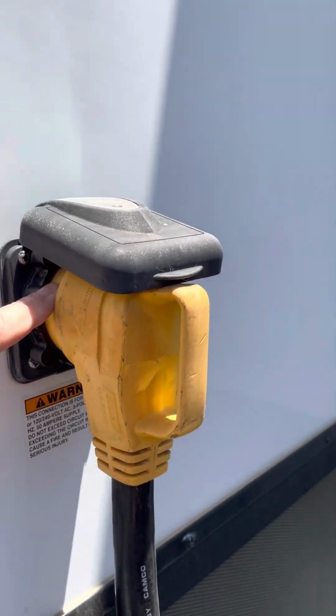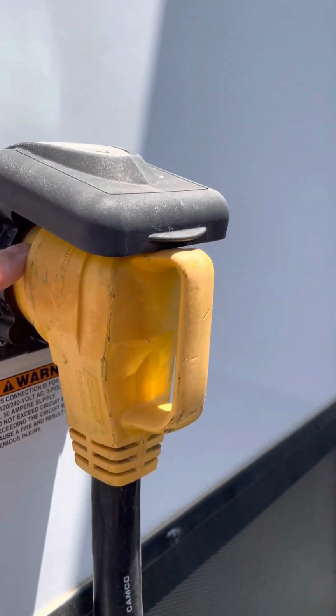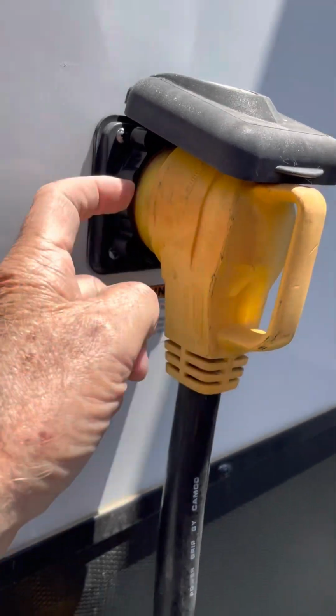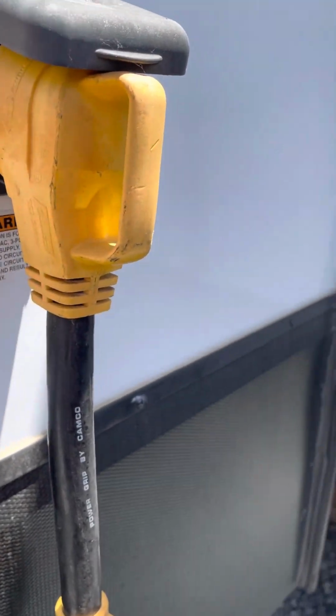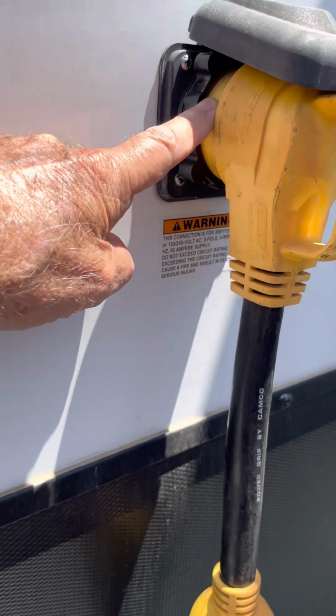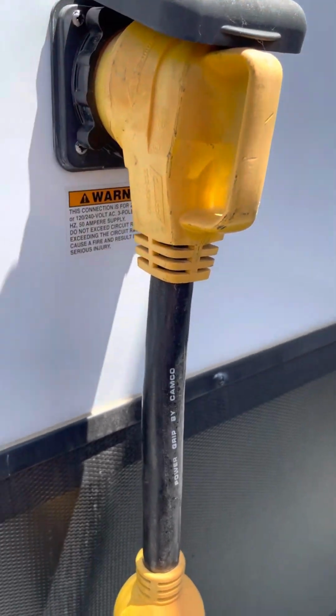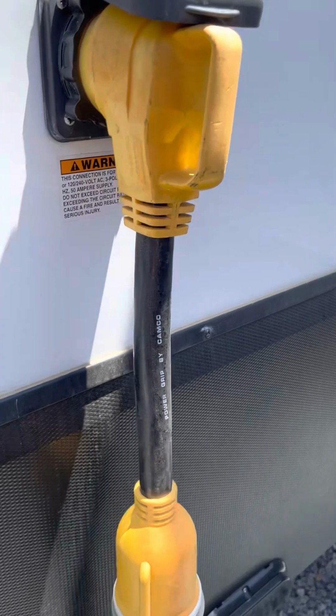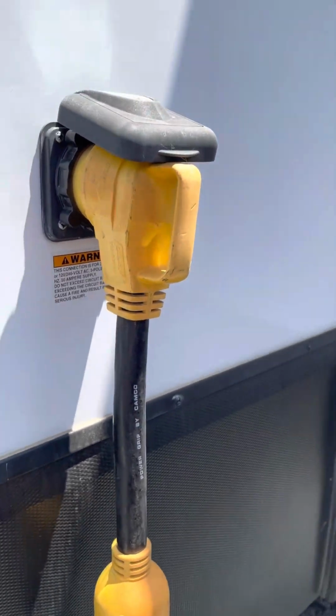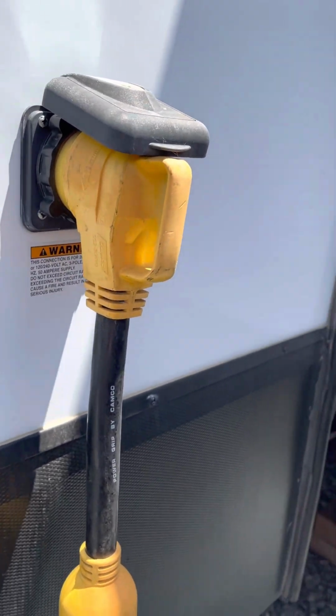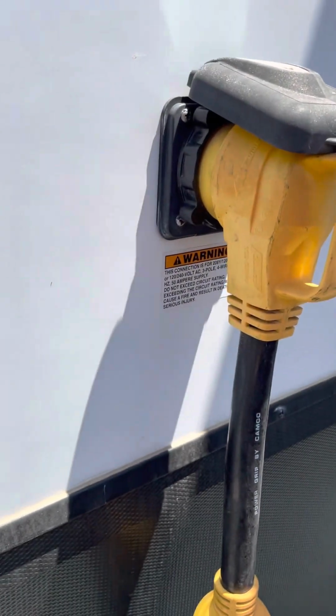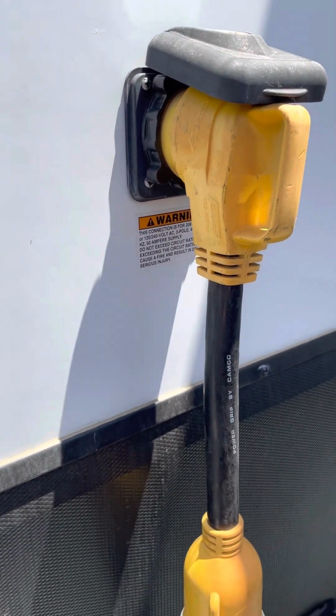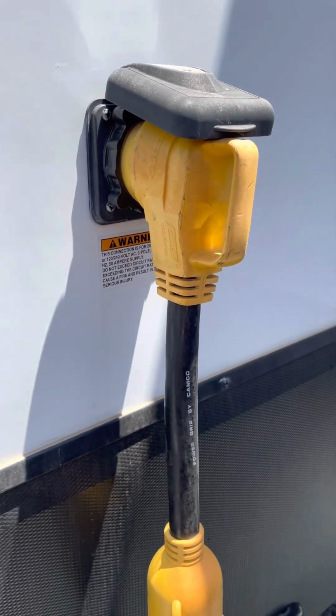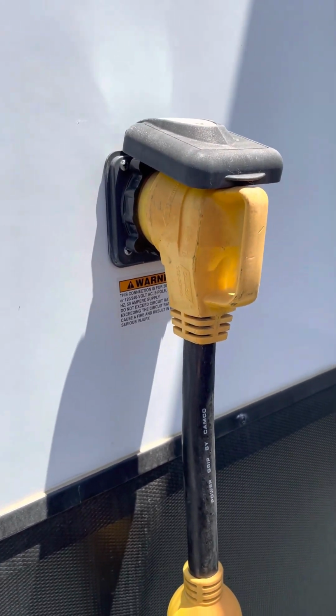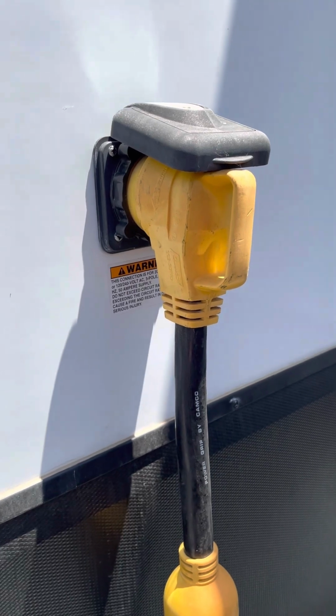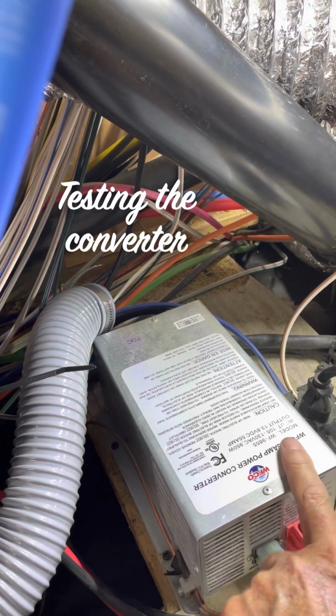Use that same two-person procedure that you used on testing the outlets in the pedestal and actually test inside this connector to make sure that you're getting power to the RV itself. If you have power here but not inside, then you'll need to start chasing wires between this outlet and the circuit breaker panel inside. If everything is working, if you have power, then the last step is to actually test the converter itself. This is the converter.